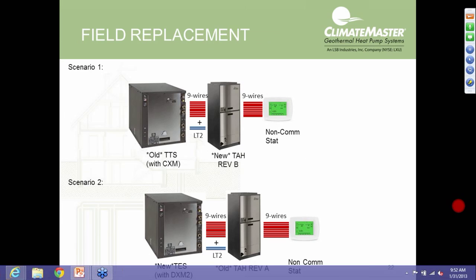Now, another scenario would be our new air handler with the AXM board in it and an older TTS with the CXM board. So again, we can go back and forth between the revision levels of the air handler. We can still use non-communication between our AXM board and our TTS, and from the AXM to a non-communicating thermostat.